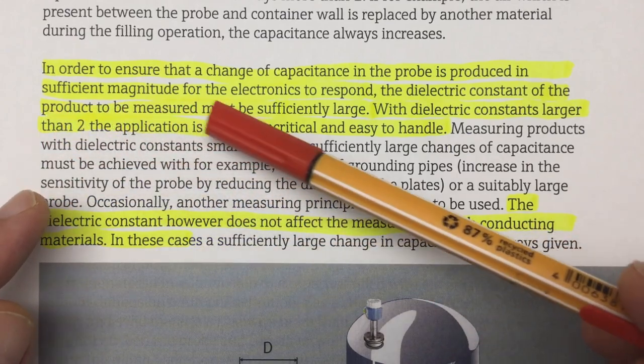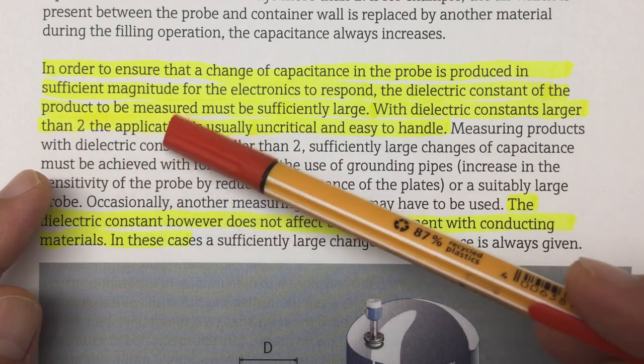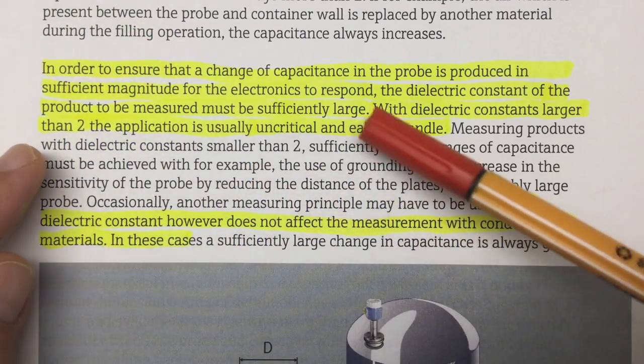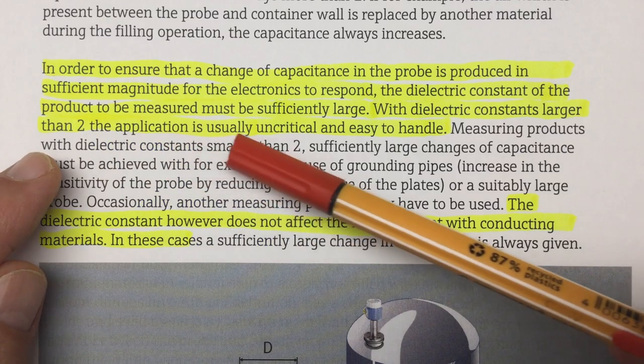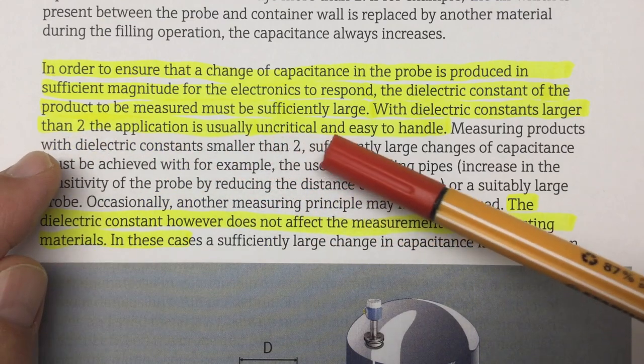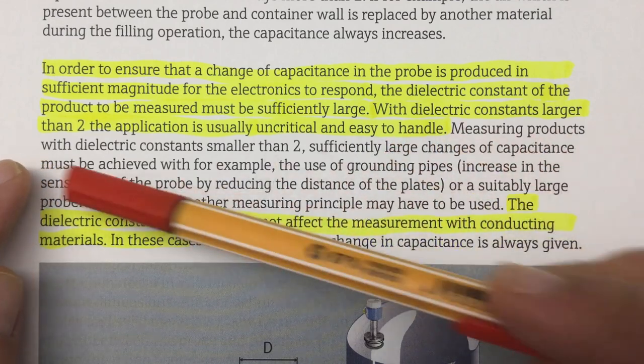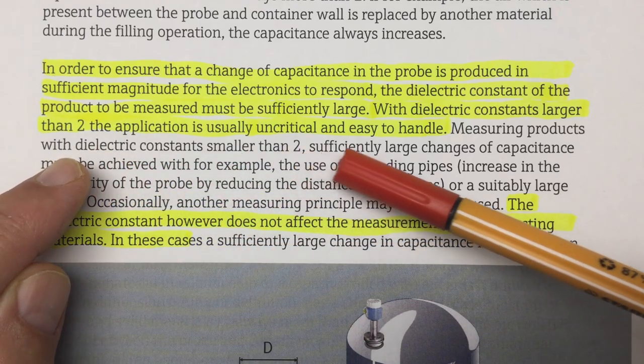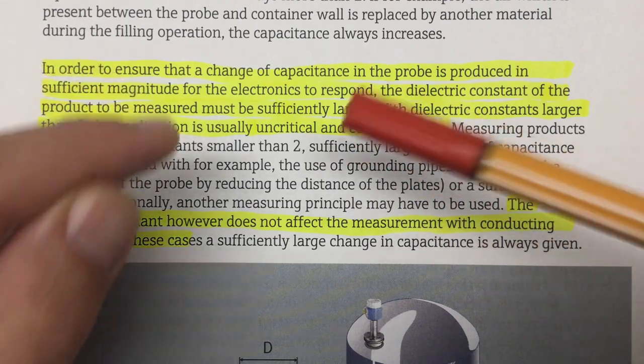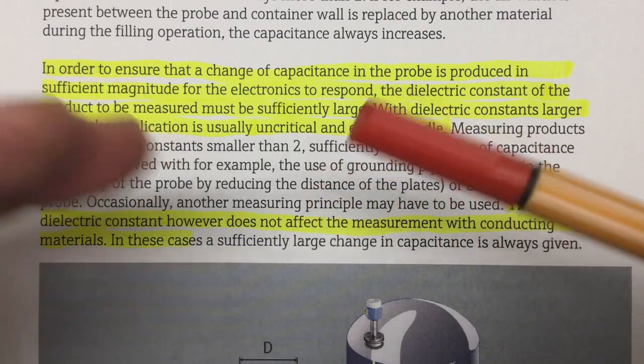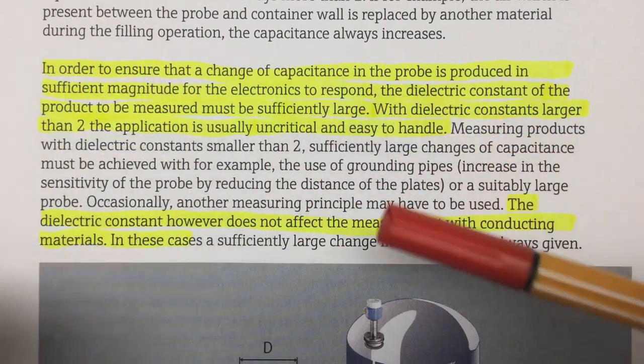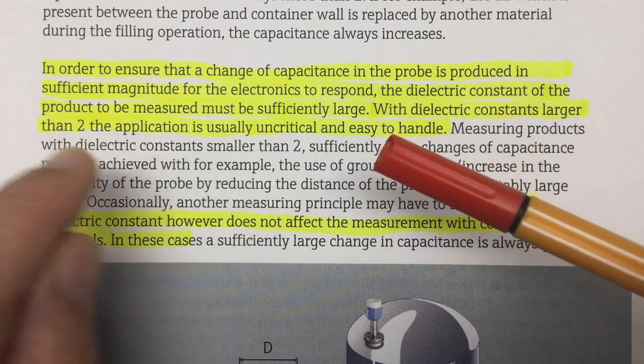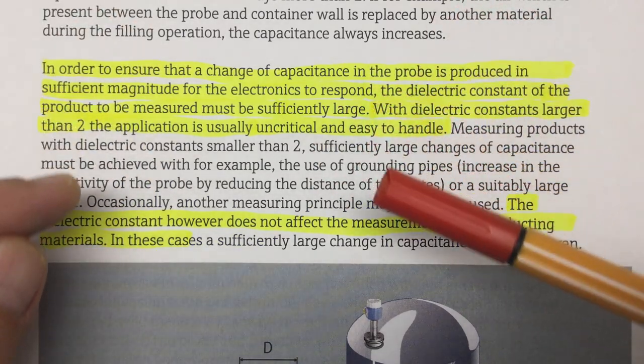However, the effect is known in the industry. I have here a paper from Endress and Hauser, a company specializing in making sensors for automation. It's called the dielectric constant DC value compendium. I put a link into the description. And at page five of that paper, you find this paragraph. It starts off talking about the dielectric constant. In order to ensure that a change of capacitance in the probe is produced in sufficient magnitude for the electronics to respond, the dielectric constant of the product to be measured must be sufficiently large. With dielectric constants larger than two, diesel for example is 2.1, the application is usually uncritical and easy to handle.